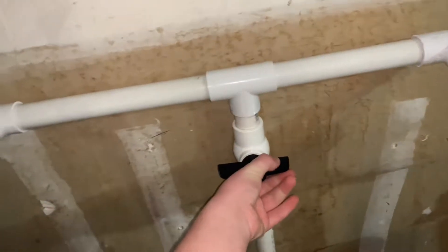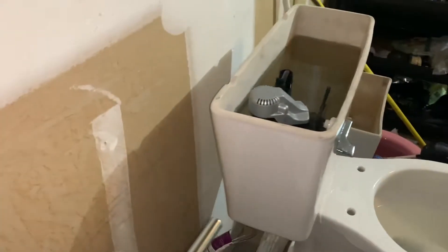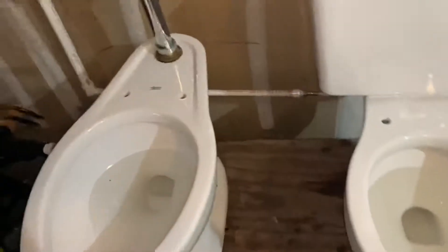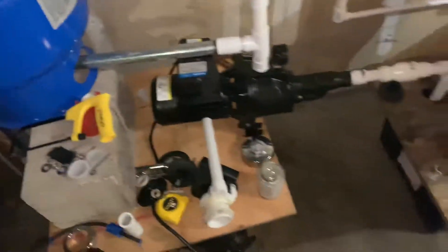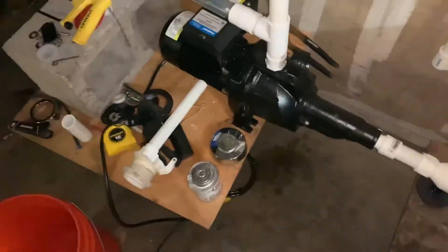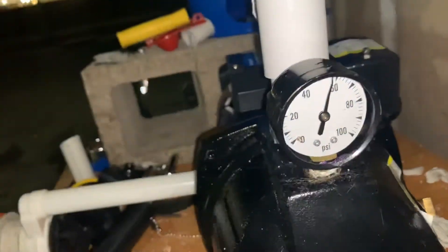This ball valve is right here. Basically, you turn it on, it lets water into the tank; you turn it off, it shuts off. Anyway, on to the flushometer. The most interesting part — how the flushometer setup works is there's a well pump right here instead of a garden hose, and this is to reuse the water so it doesn't get wasted. There's a check valve right there, and you can see it's at about 60 PSI — like 59 PSI — and that's just enough to power these two toilets.